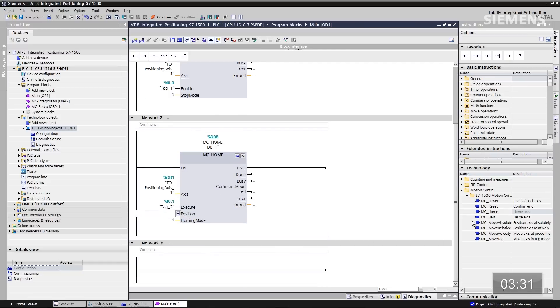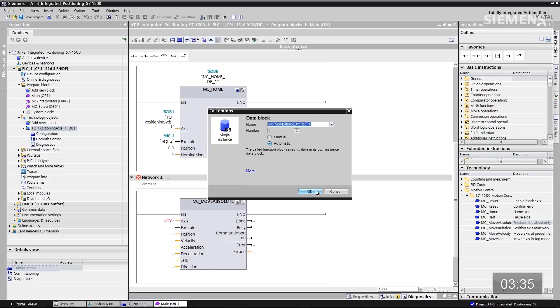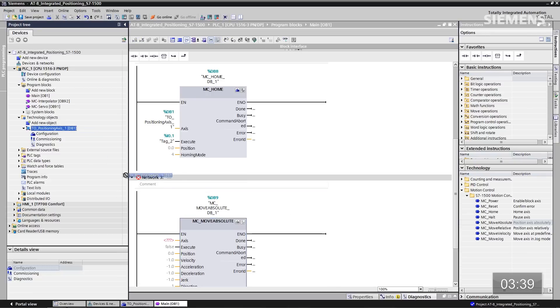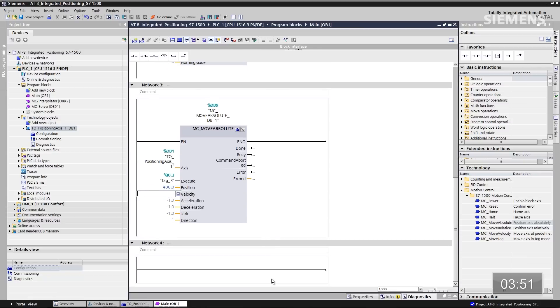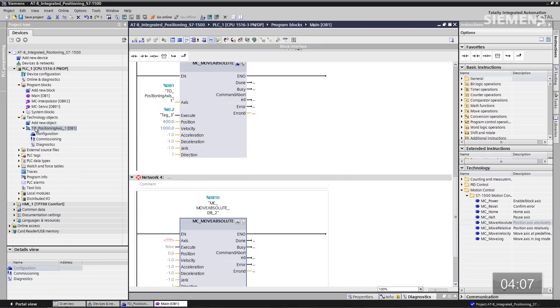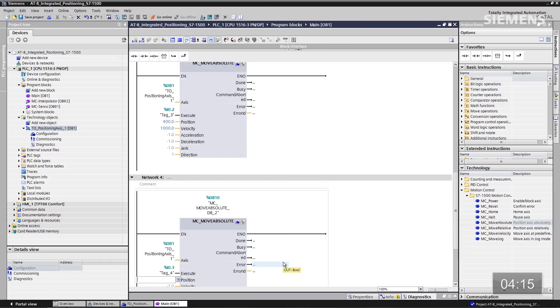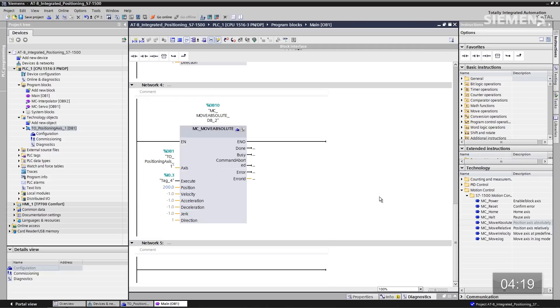Now I'd like to do some absolute moves. Let's drag and drop the first MC_MoveAbsolute in, accept the default data block, and tie it to our TO. The execute input is going to be input 0.2, the position is going to be 400, and the velocity is going to be 1,000. I could use tags instead of absolute values, but in this instance I'm going to use absolute values. Let's do another absolute move — accept the default data block, tie it to the TO, execute with input 0.3, and the position is going to be 200. I'm going to use the standard velocity from the technology object. You'll see negative ones next to acceleration, deceleration, and so on — these are derived directly from the TO.